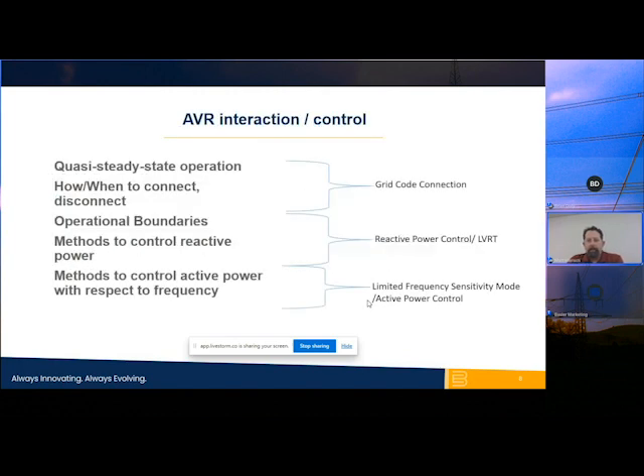So with these three main elements, some of the things we're going to look at is the quasi-steady state operation of that particular machine, and this is for grid code connection or disconnecting. Based upon the operation of that machine or the condition of the grid, it will tell us how and when to connect or disconnect to the power grid. We'll also look at the reactive power control, and we'll look at those operational boundaries of where the voltage regulator is going to put that machine to operate, again, to support the power grid, and the methods that we can use to control that reactive power. We're also going to talk about the limited frequency sensitivity mode and the active power control, and those are methods to control that real power, again with respect to the grid frequency. So in all these conditions, we're really monitoring that utility grid, and the voltage regulator is going to take the data that it sees and do control based upon what the grid conditions are.